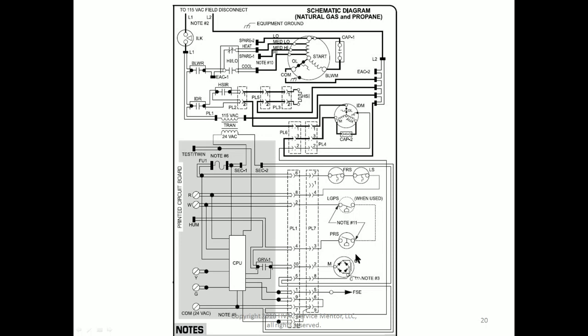Next, let's look at our power supply. Yes, we have 120 volts landing on the control board at these two terminals here, but that's not what powers the board. The board is powered by 24 volts landing on the SEC1 and the SEC2 terminals. That's what powers the control board right there. Next, it goes through a fuse. Then the 24 volts leaves the board, goes through a flame rollout switch, goes through a limit switch, comes back to the board, and lands on the R terminal.